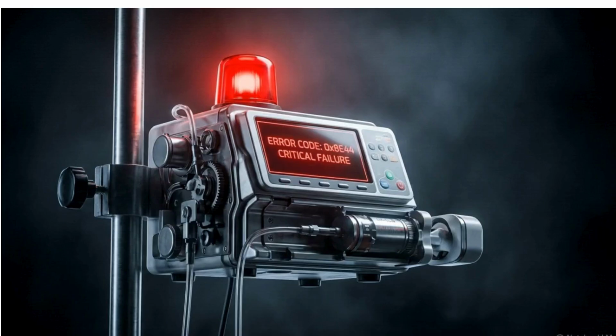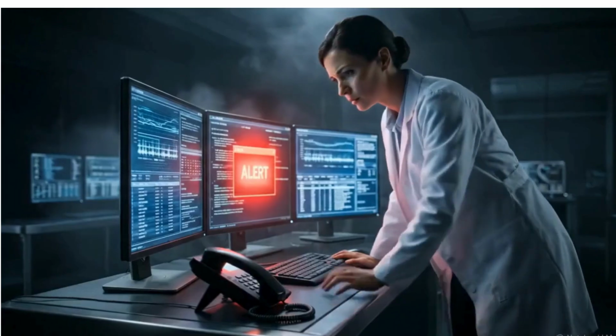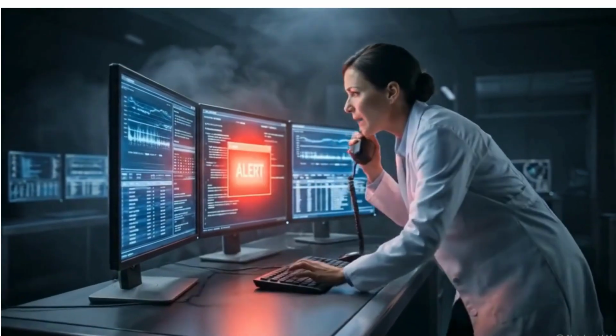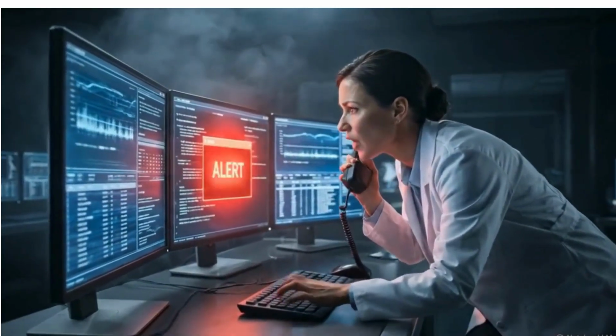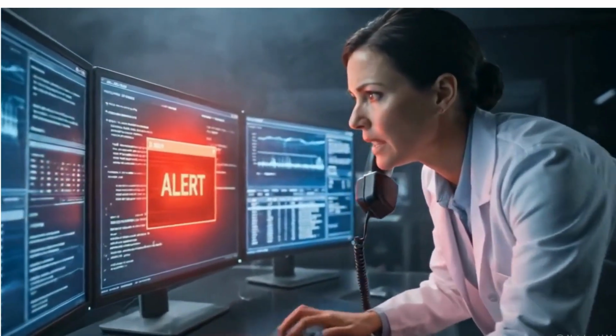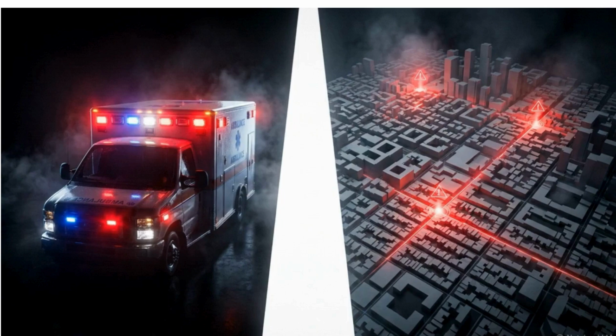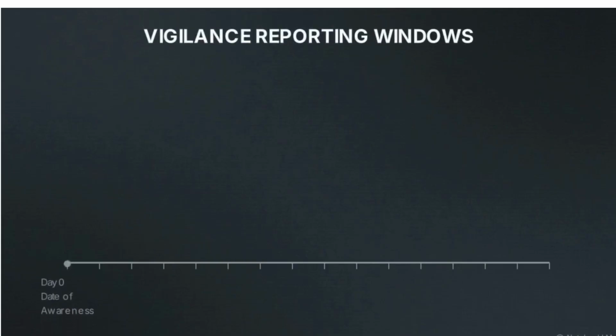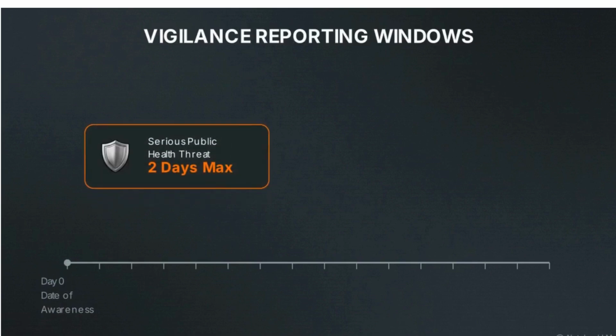When a physical failure does happen, it triggers a process called vigilance reporting. The regulatory clock starts ticking the absolute second a manufacturer learns their device directly or indirectly caused a death, a serious deterioration in health, or a threat to public health. This timeline illustrates the strictest of those rules. Under the EU MDR, if a failure poses a serious public health threat, like a widespread contamination issue, the manufacturer must notify authorities immediately, with a hard deadline of just 2 days.